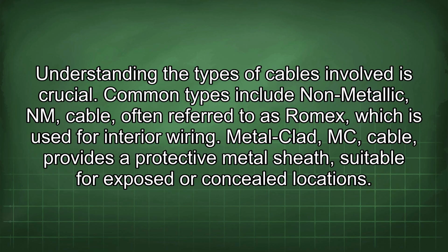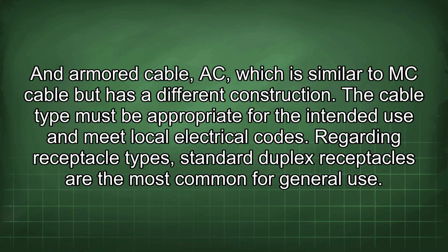Understanding the types of cables involved is crucial. Common types include non-metallic NM cable, often referred to as Romex, which is used for interior wiring. Metal-clad MC cable provides a protective metal sheath suitable for exposed or concealed locations. An armored cable, AC, is similar to MC cable but has a different construction. The cable type must be appropriate for the intended use and meet local electrical codes.